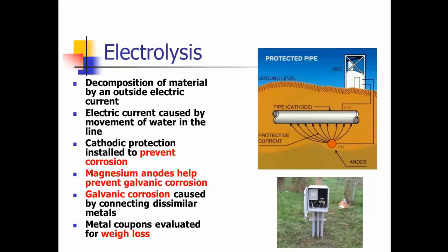Electrolysis is the decomposition of material from an electric current in the water that's produced by the movement of the water. They use cathodic protection where they have a sacrificial anode, and that will dissolve. Magnesium anodes help prevent galvanic corrosion, and the galvanic corrosion is caused by dissimilar metals coming in contact, connecting the two. They use metal coupons also to evaluate the weight loss.